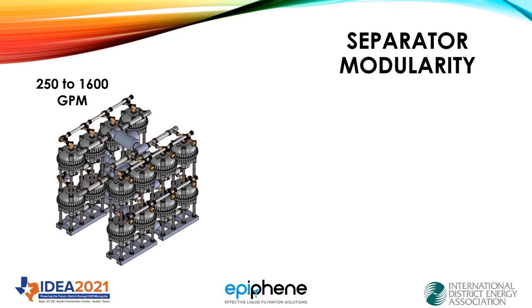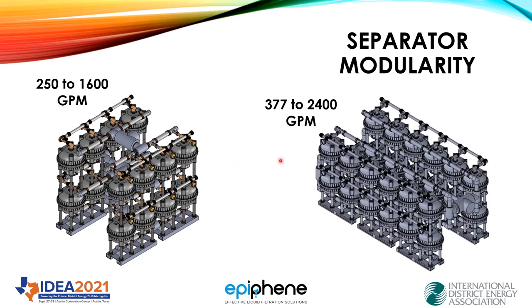So let's look at the modularity of these filter tanks. We can do a simple two-tank system, a four-tank system, a six-tank system, an eight-tank system, or take the eight tanks and put them in parallel. Depending on the flux we are looking for and the micron removal, this can go anywhere from 250 to 1,600 gallons a minute. Another similar configuration using pairs gives us basically 400 to 2,400 gallons a minute with 24 tanks.